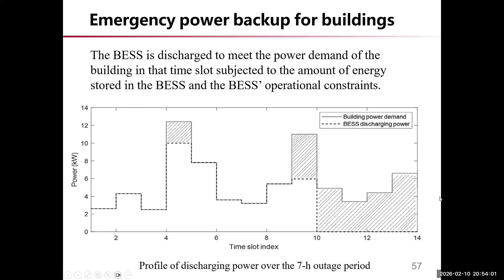Here is a simple rule-based strategy for emergency power backup for buildings. The BESS discharges to meet power demand at the time slot when we don't have enough energy, and we save it at other times. Here the dashed line is the BESS discharge power. In the first time slot we have a higher power need for the building, but the energy from the grid is not enough, so we use the BESS power to support that demand. This is similar for the rest of the time.